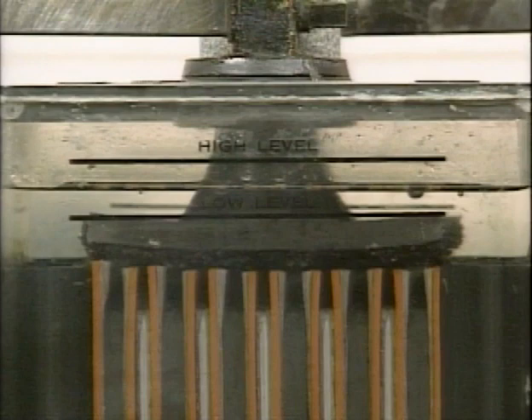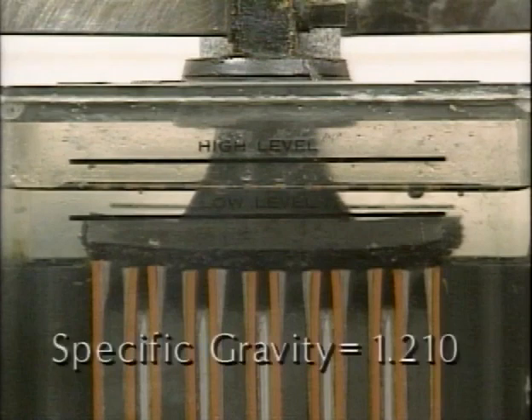As you may know, the electrolyte in a cell is composed of sulfuric acid and water, and the specific gravity of a charged lead-acid cell is typically around 1.210.